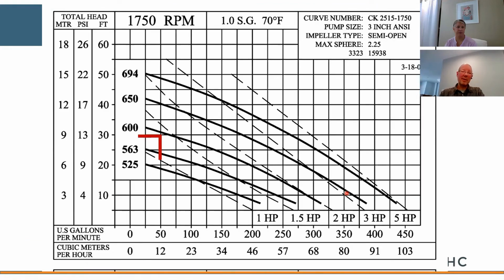So let me just make up a duty point, and then we'll address the poll here real quick. It's not uncommon to see some pretty ugly selections with Sump and Sewage. So in this case, I'm making up a condition of 50 gallons a minute is what we need out of our pump at about a 30-foot lift. Which puts me back, we would call this to the left of our pump curve. We're not out here to the right, or what we might call a best efficiency point. But notice there's no efficiencies to reference. So that takes that out of the equation. The question is, what horsepower would we use for 50 gallons a minute at 30 feet of head?